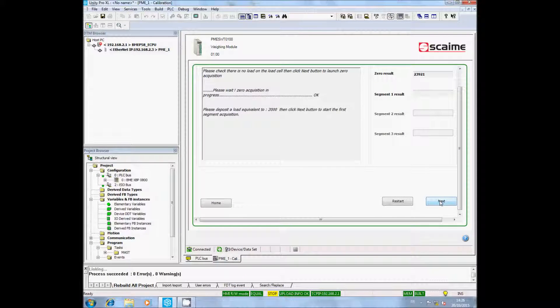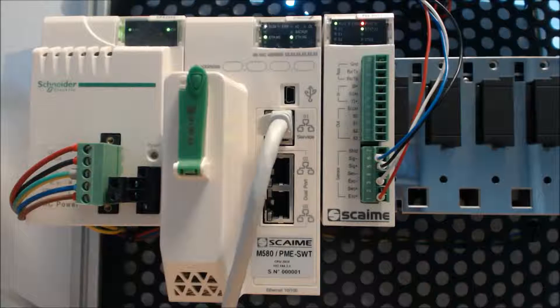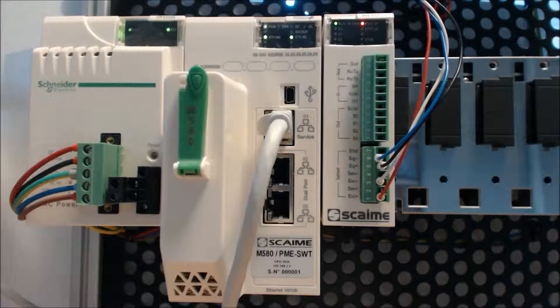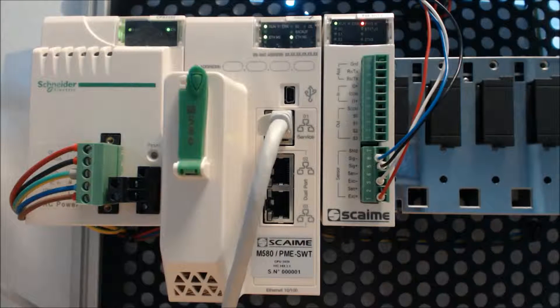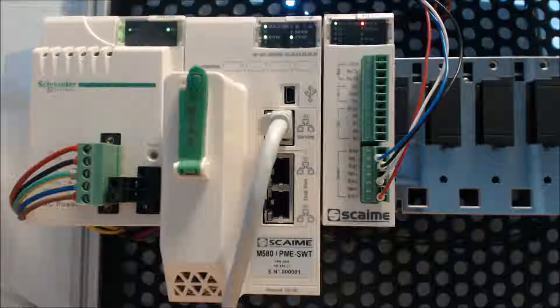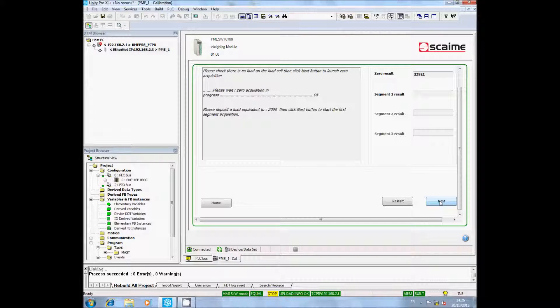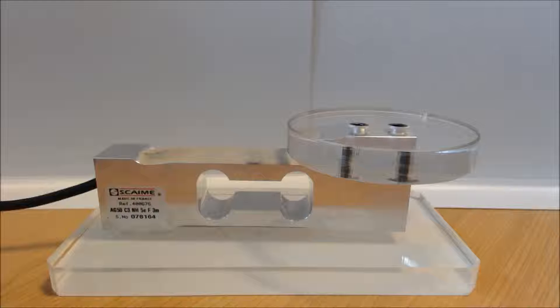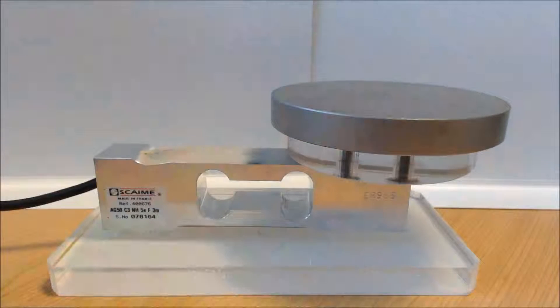If you look at your PMESWT, you can see that the status LED is blinking less quickly. The software asks you now to deposit a weight of 2000. You can go on.